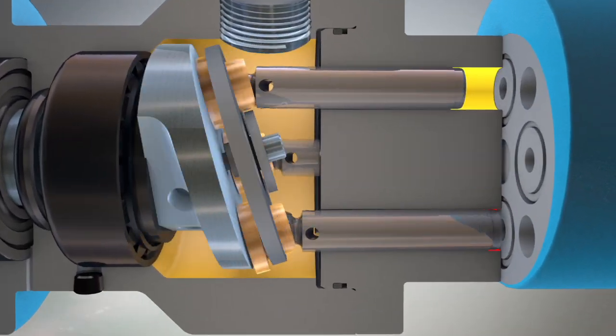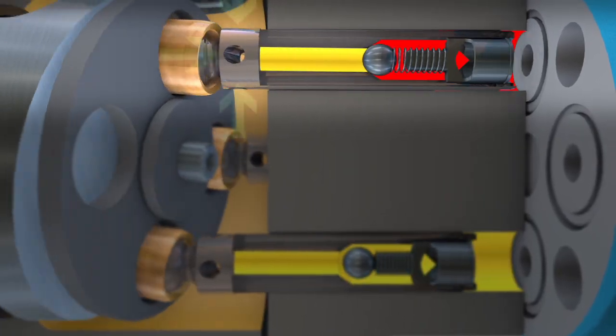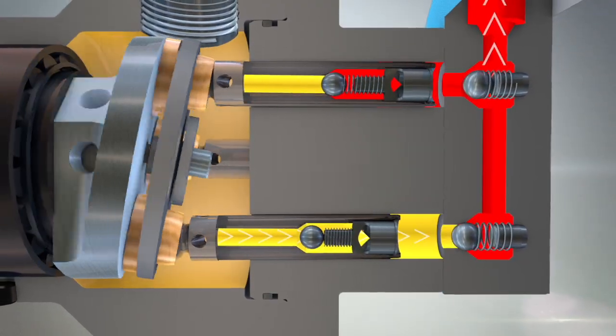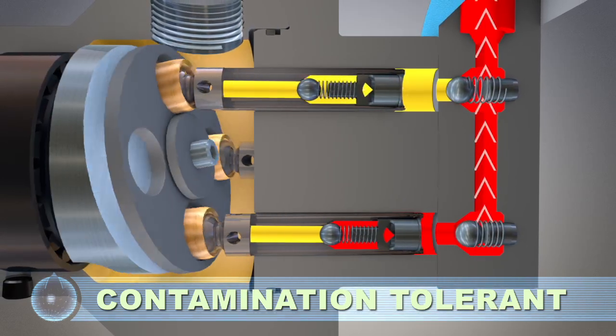During the suction stroke, fluid moves into the pumping chamber through a large flow path. During compression, the inlet check valve closes and pressure in the chamber rises. When load pressure is reached, the outlet check valve opens. The check balls reseat during each cycle for even wear.